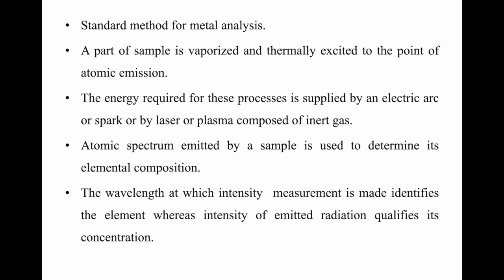Atomic emission spectrometry is a standard method for metal analysis. A part of the sample is vaporized and thermally excited to the point of atomic emission. The energy required for these processes is supplied by an electric arc, spark, laser, or plasma composed of inert gas. The atomic spectrum emitted by a sample is used to determine its elemental composition. The wavelength at which intensity measurement is made identifies the element, whereas the intensity of emitted radiation qualifies its concentration.